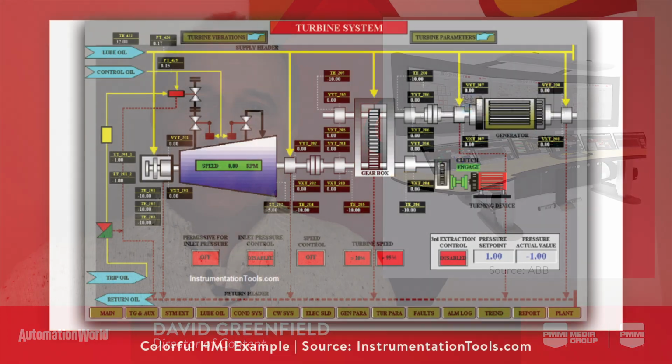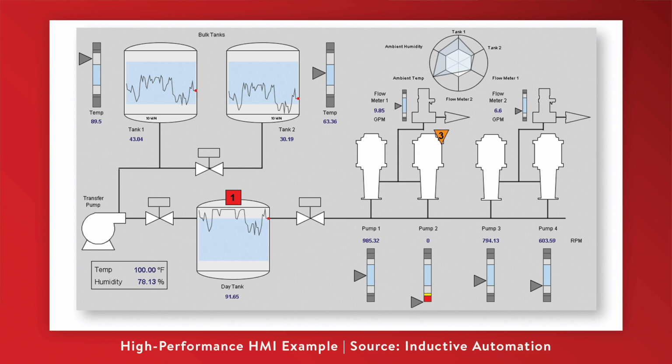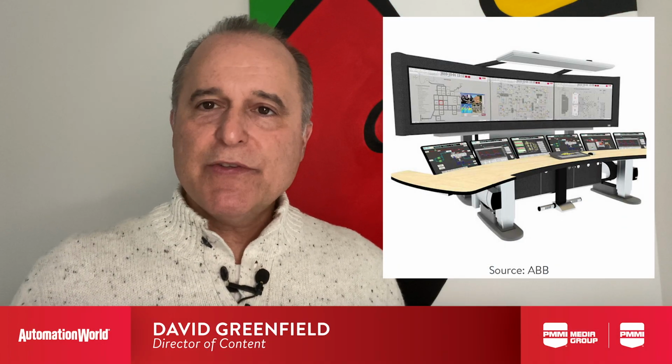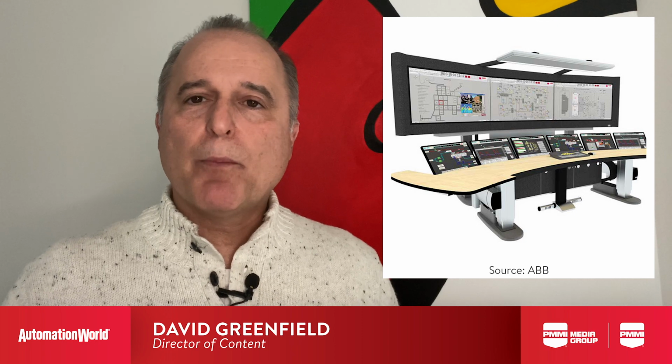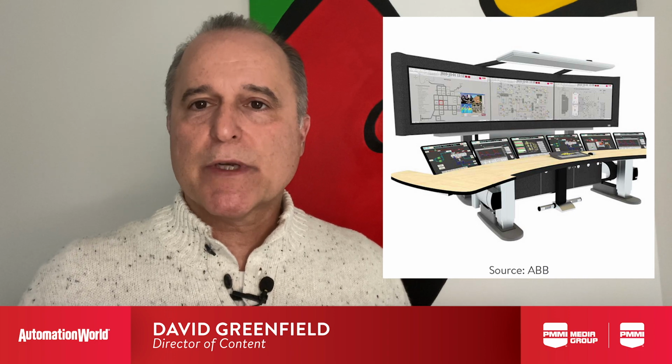For example, each device or piece of equipment shown on the HMI screen won't be represented with different colors, and you won't see pipes filling with blue or green fluid or flames underneath a tank indicating an active boiler operation. Instead, a high-performance HMI screen will be primarily gray, with just the devices or systems requiring attention highlighted in any kind of attention-getting color. Now, proponents of high-performance HMIs say the grayscale screens with minimal color enable better situational awareness for operators by better directing their response to high-priority problems.